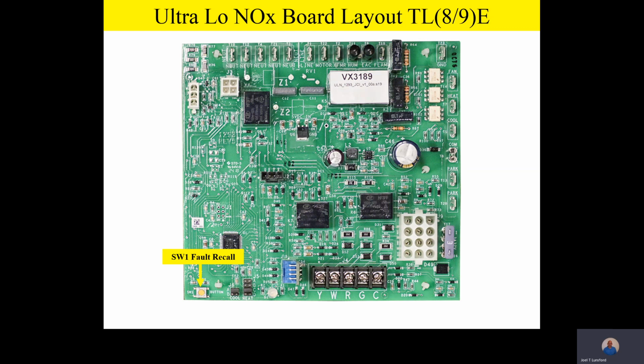In addition, if you hold the SW1 switch down, the fault recall switch, for about 10 seconds, it clears the memory. And we recommend the technician does that. As a matter of fact, if he's out on a service call and he repairs the furnace, once he repairs that furnace, we always like to have him clear that memory on the fault recall. That way it'll have only fresh fault codes in there if there are any more fault codes. So again, to reset that fault memory, hold that button down for about 10 seconds.